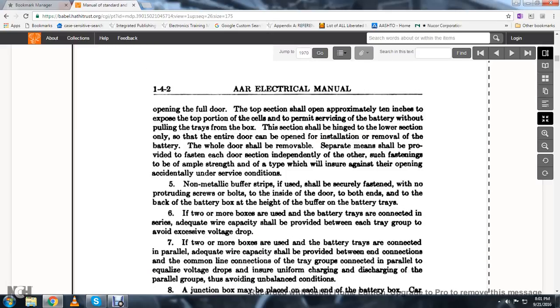The top shell section shall expose approximately 10 inches of the top portion of the cell for servicing the battery without pulling out the trays from the box. The section shall be hinged to the lower section only so the entire door can be opened for installing and removal of the battery. Separate means shall be provided to fasten each door section independently, such fastening to be of ample strength to ensure against accidental opening under service conditions.